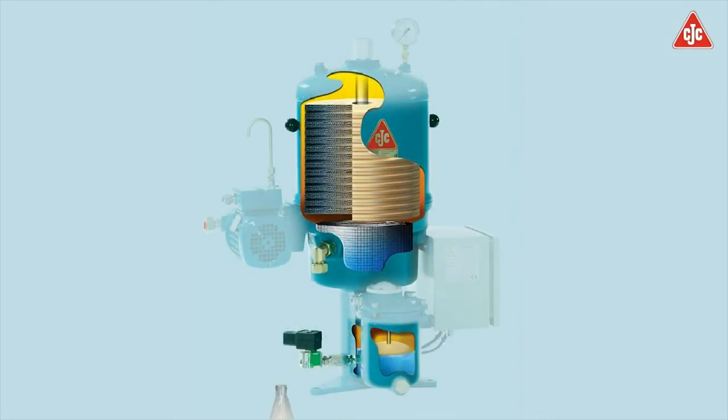A large amount of water in the system is removed by our coalescing system. Water aggregates into droplets, sinking down into the coalescing element. The droplets settle in the bottom of the filter housing. The water is automatically removed through a water discharge.